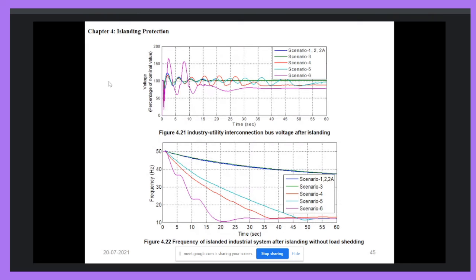Okay. So after the islanding, you can see in figure 4.22 the frequency of the islanding industrial system. Okay, here we can see the frequency for scenario 6, in which only one industrial generator is in operation, is the severe variation of the frequency, because in-plant generation is smaller as compared to other operating scenarios. In scenarios 1 and 2, all the 3 generators are in operation, and in operating scenario 6, only one generator is in operation.